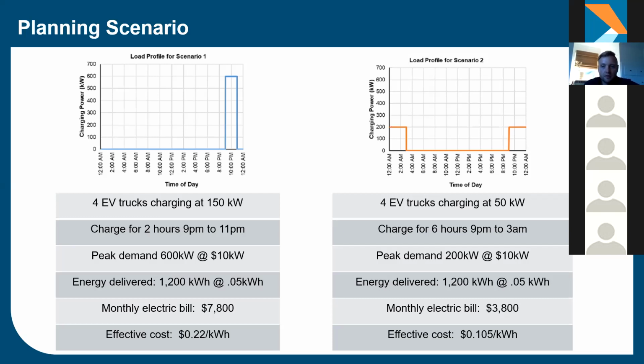So here's how you can charge these trucks. On the load profile for scenario 1, the blue one on the left, you would charge your 4 trucks for 2 hours at the same time, from 9 p.m. to 11 p.m. Your peak demand would be through the roof. You'd have 4 fast chargers. Your peak demand would be 600 kW. Your energy delivered would be 1,200 kilowatt hours, and your bill would be effectively $7,800 a month, or 22 cents per kilowatt hour.